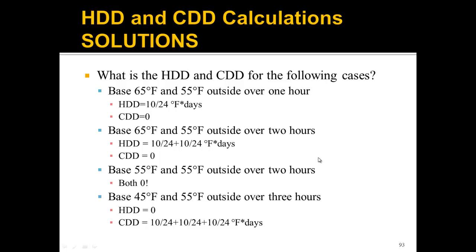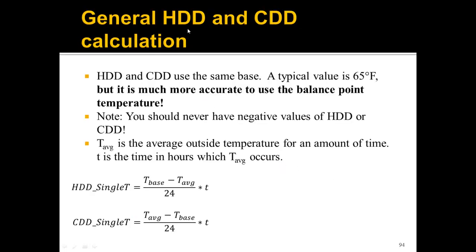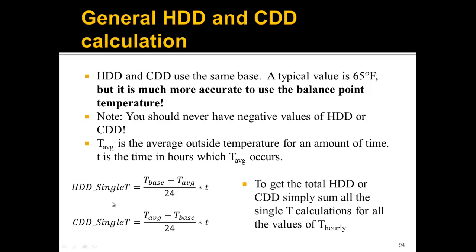For non-hourly temperature data, instead of T_hourly we use T_average — the average outside temperature for any amount of time — multiplied by t, the duration in hours. The formula becomes HDD = (T_base − T_average) × t / 24 and CDD = (T_average − T_base) × t / 24 for each time period. To get total heating or cooling degree days, sum all individual time-period calculations.